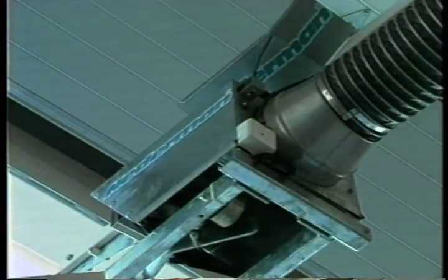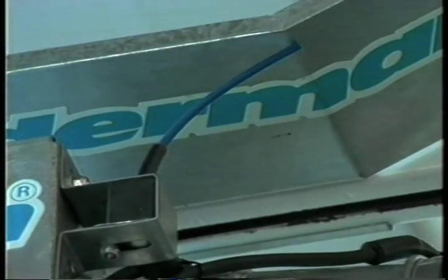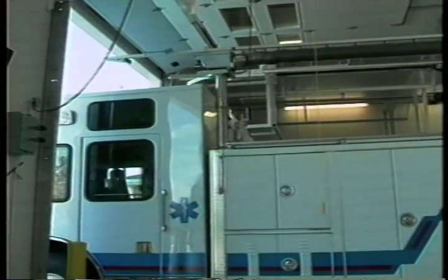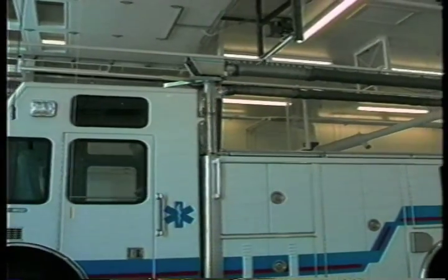Upon vehicle exit, the electromagnet is de-energized as a micro switch contacts the disconnection plate. The disconnection plate is mounted to the guide track near the door exit. Magna stack, for vertical exhaust stacks, is a system that is automatic, completely self-aligning, and very compact.